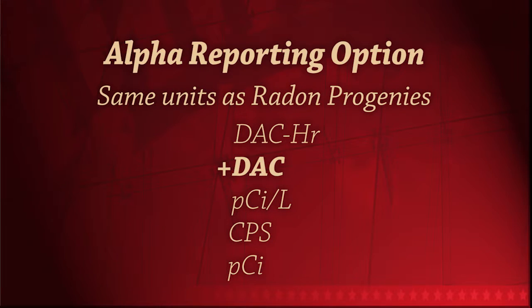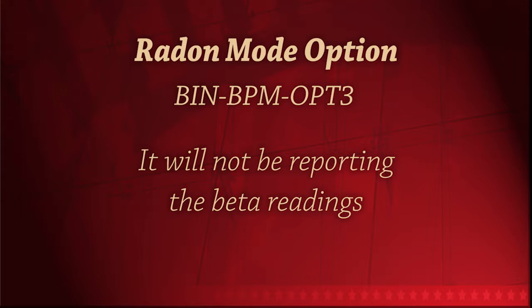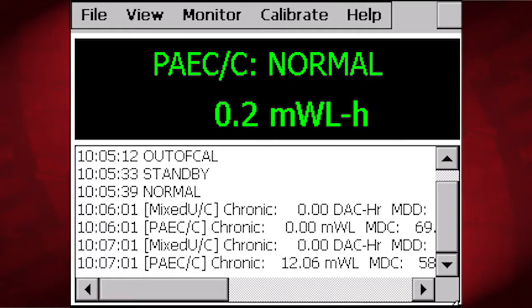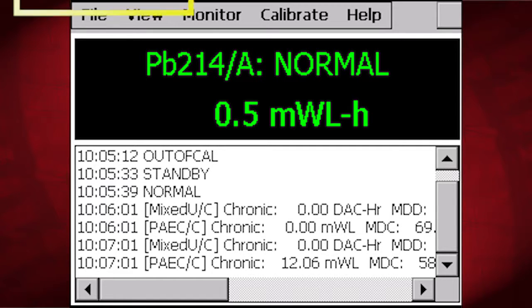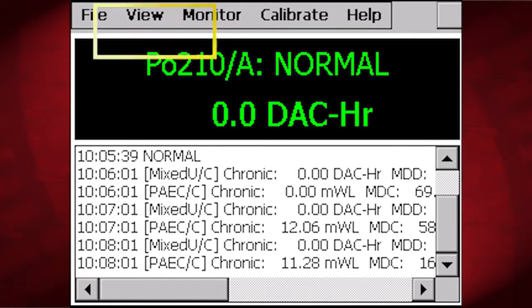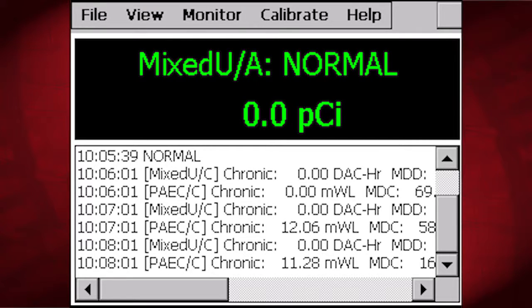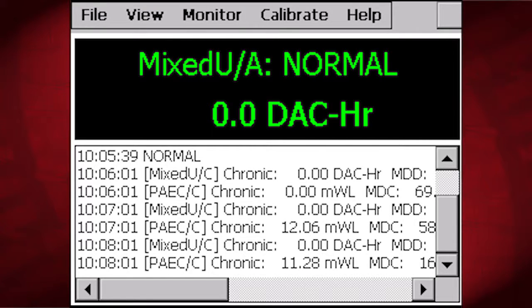Each of the isotopes of interest has the same units available as the radon progenies, with the addition of reporting in DAC. If the instrument is ordered with the radon mode option, it will not be reporting the beta readings. Instead, it will report the PAEC, or potential alpha energy concentration. The units for PAEC are milliworking level hour, milliworking level, counts per second, and picocuries.